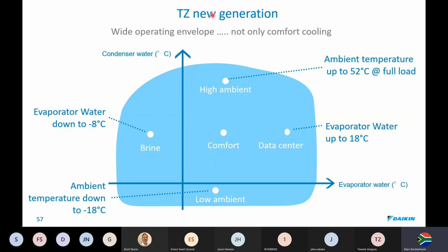And on these specific chillers, being inverter, we can go down to minus 8 degrees with brine or glycol mixture. Some of our chillers, depending, like scroll compressors, they generally can go down to about minus 15. So you can't go that cold with screw compressors. It's just the thermodynamics and the design process. It is give and take. There's a lot better control on a screw compressor for loading and unloading. With scroll compressors, it's either on and off, unless you go for the fully inverter. But screw compressors are not really designed to switch off. They're designed to run in the morning to night and modulate by unloading their compression cycles. They don't like to really run on and off.